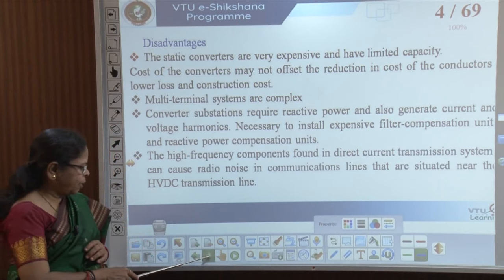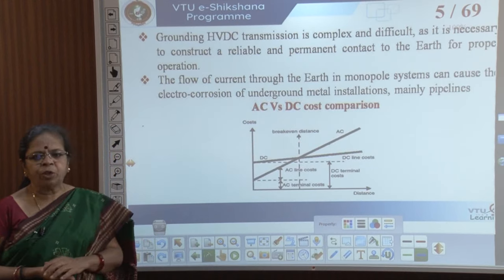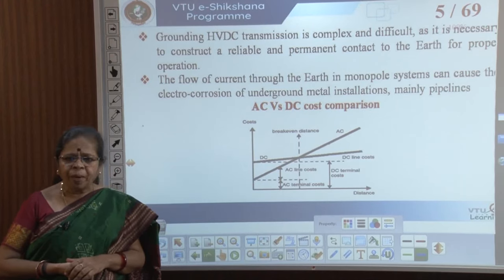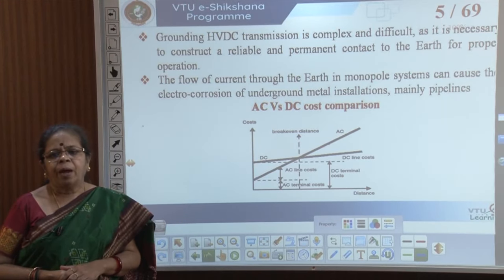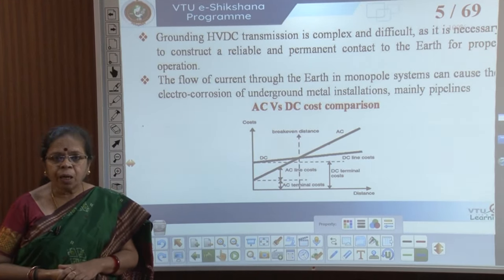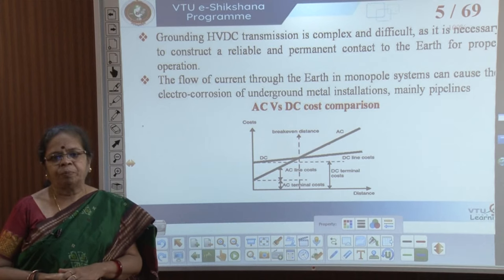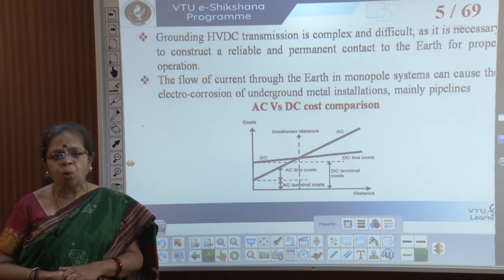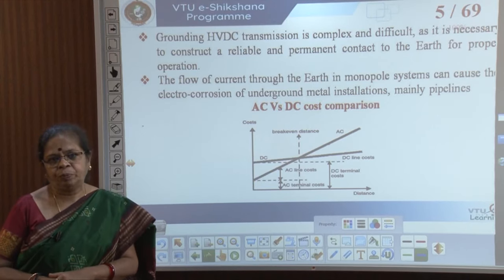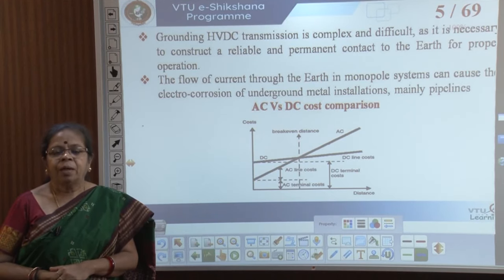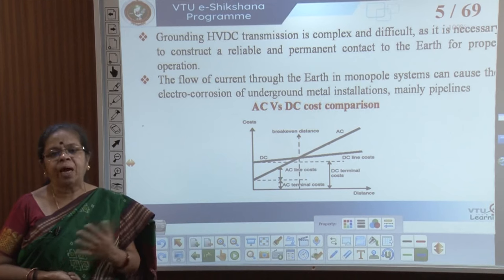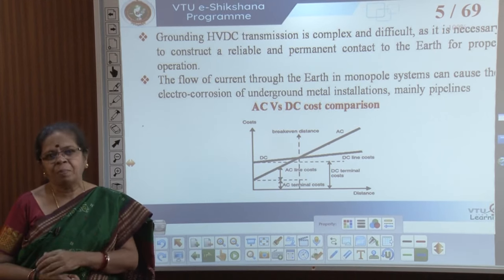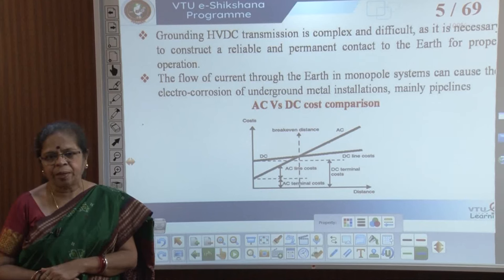Those are some of the major disadvantages of HVDC systems. Additionally, grounding is also complex, difficult, and very important. The flow of current in a monopole, where the ground is used as a return path, can cause a lot of erosion in underground metal installations such as water pipelines and other pipes laid underground.